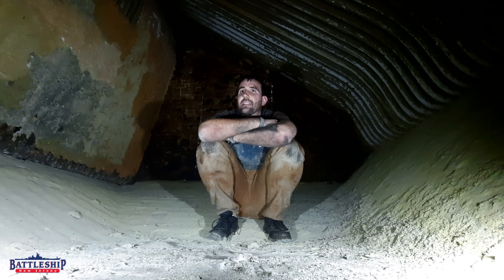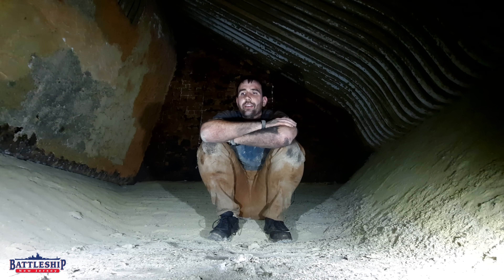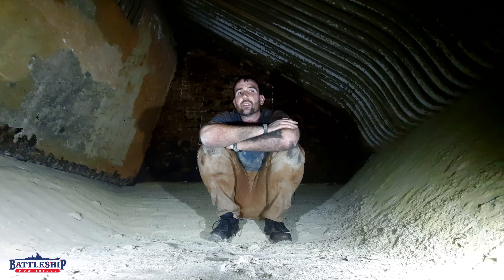If we were to shoot this at 600 PSI into our turbine blades, the water droplets would be hard enough to damage the blades at that speed. So it goes next door into the superheated side. We've got five burners here spraying fuel into the saturated steam side, and there are another four burners on the other side making superheated steam. That heats it up to 850 degrees — at that point it's 99% dry steam, with enough moisture removed that we can now shoot it into the turbine blades.